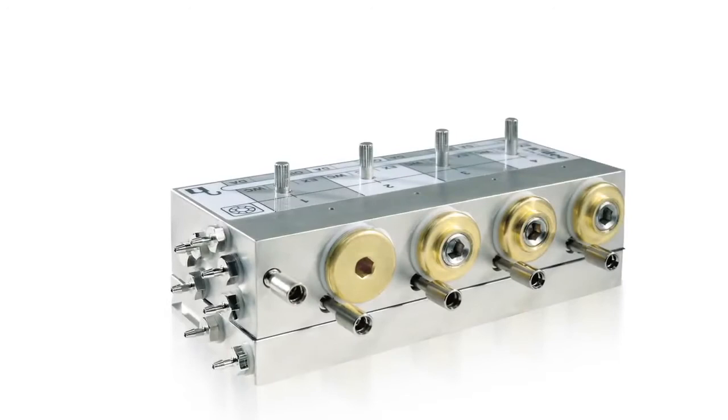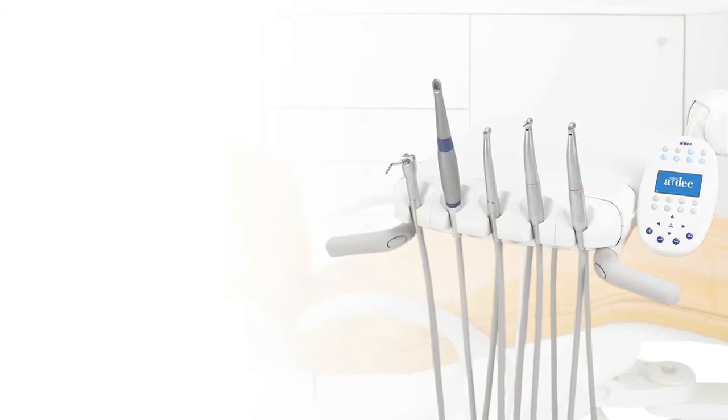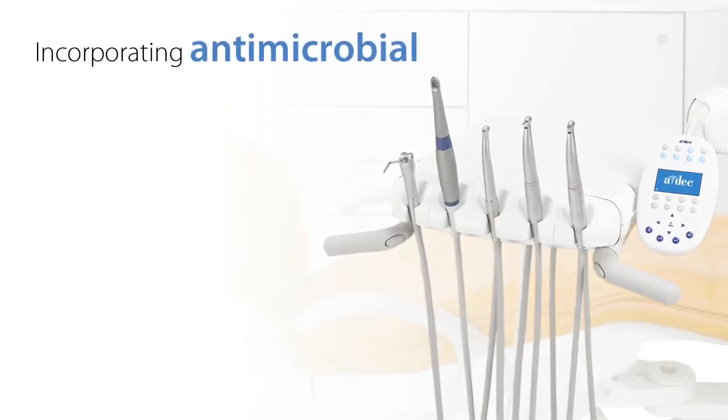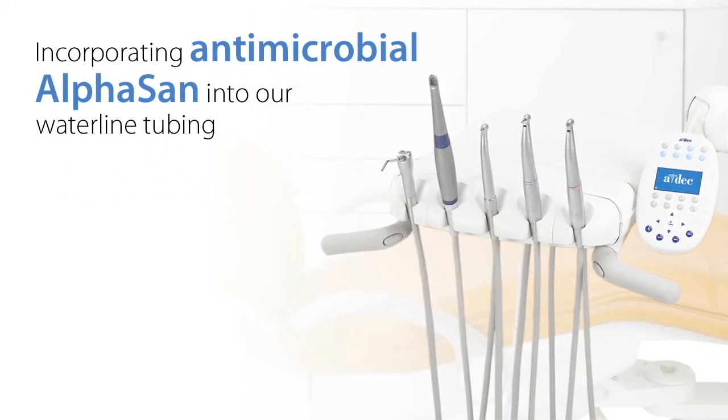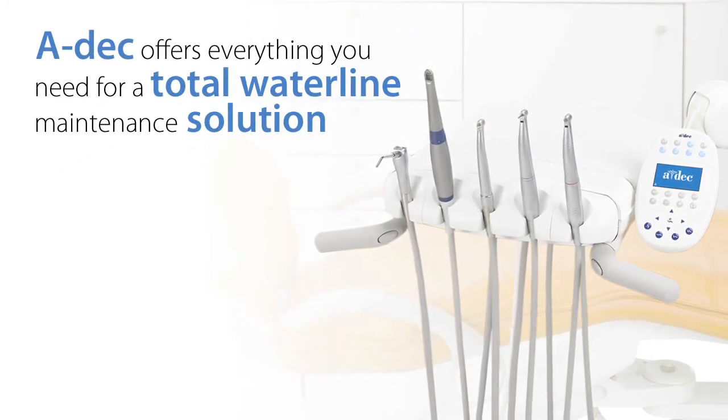That means it avoids having stagnant water just sitting somewhere in the dental unit, which could potentially lead to a hospitable environment for biofilm formation. And yet another example of our system approach is incorporating antimicrobial alpha-san into our water line tubing. A-dec offers everything you need for a total water line maintenance solution.